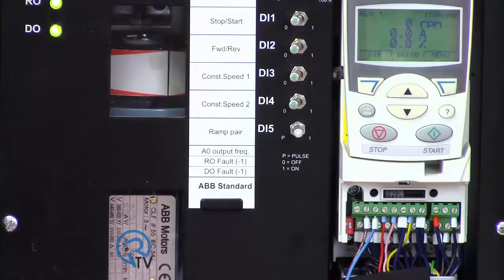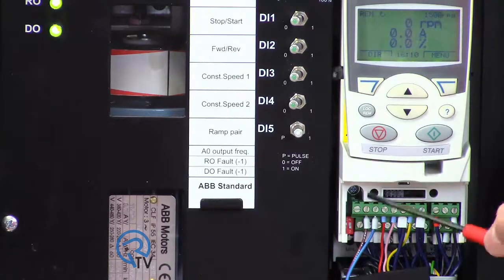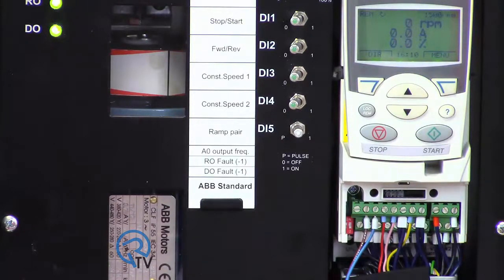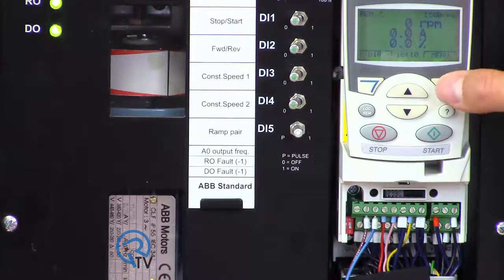We will set the VFD to have a variable speed between 200 and 1400 RPMs based on that sensor input. Verify that the analog input selector is set for current. Note that the two inputs are independently selectable. After setting all motor parameters, it's time to scale the analog input.